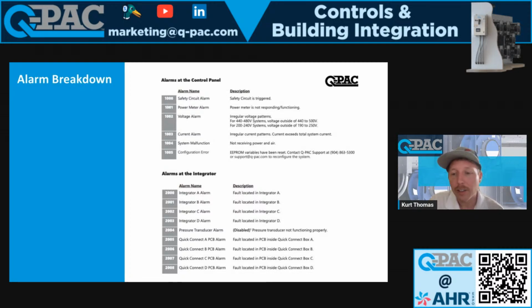Craig White is asking, what's the purpose of the interlock toggle? So the interlock toggle basically just turns the functionality on or not, right? So if you want to use the interlock, then you can enable it for use at the HMI, or you can enable it for use via BACnet. So once it's set, it's usually set, and you don't toggle it on and off. I can't think of a reason to toggle it on and off, but there are 2 different ways to turn it on. So thanks for your question.